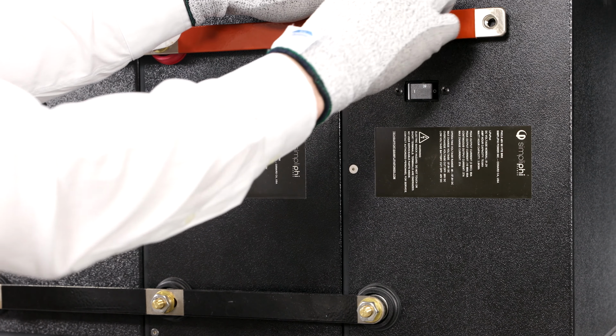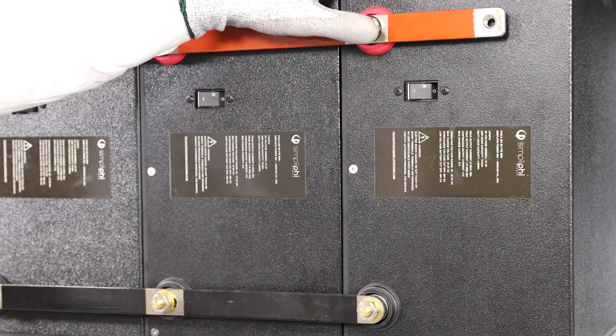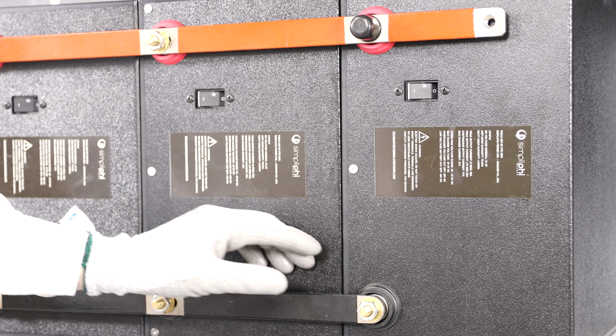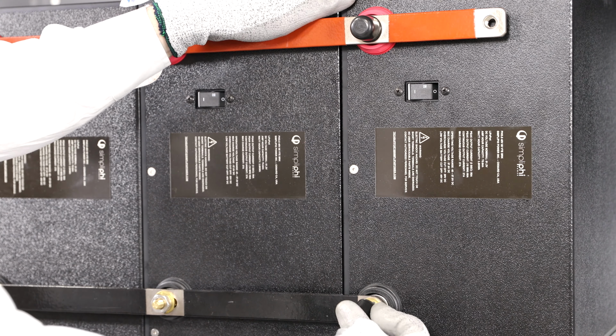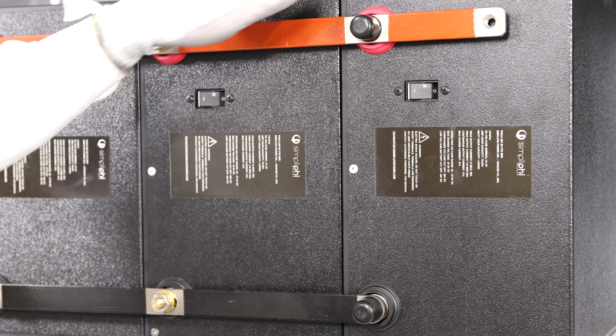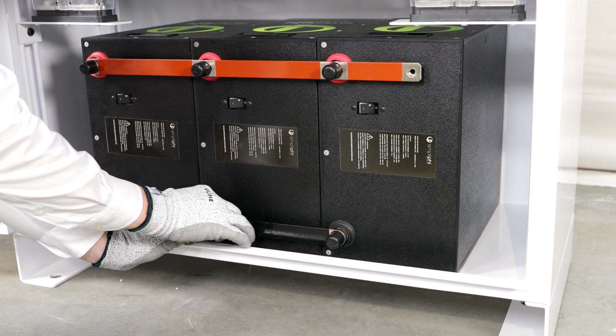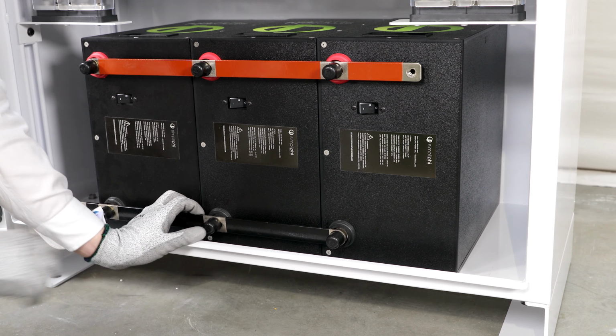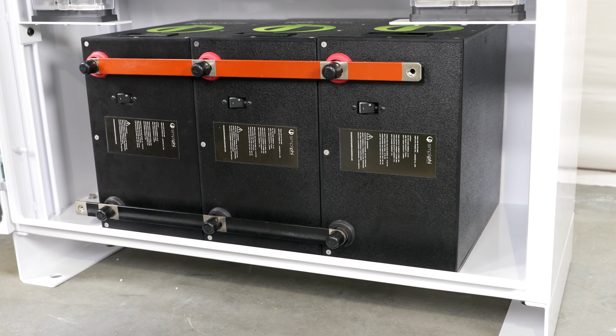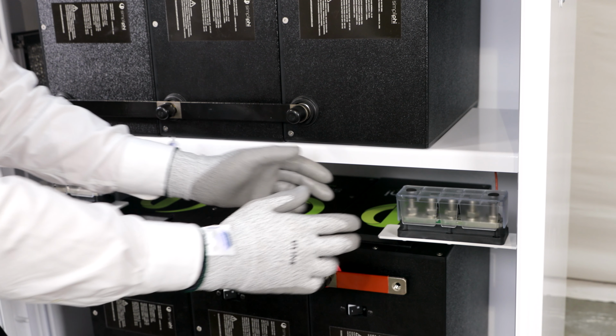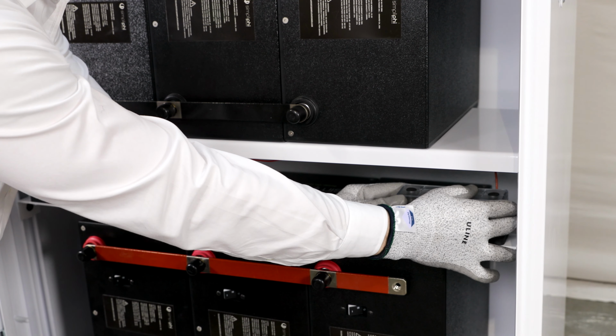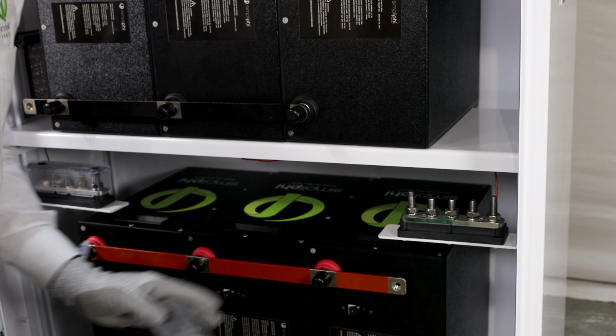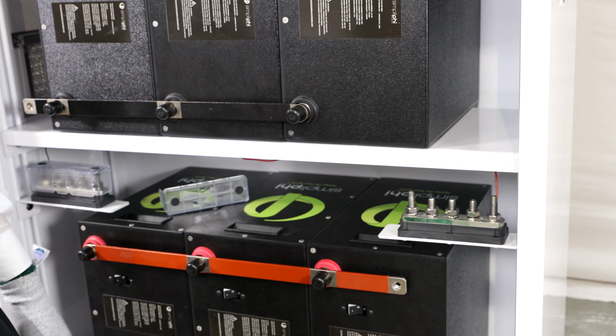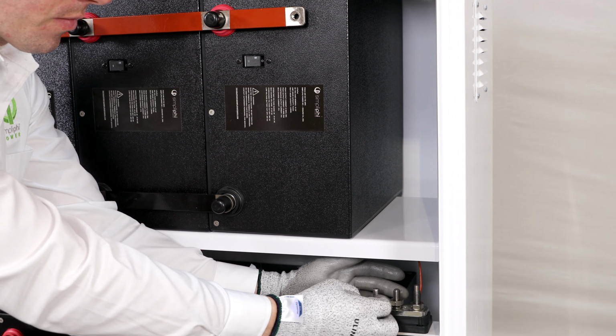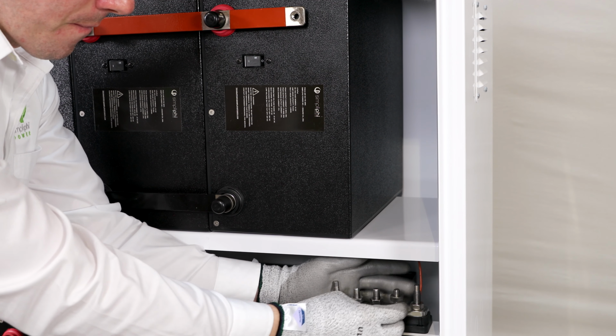After securing the bus bar to all battery terminals, place the black terminal caps over the terminals, ensuring to cover the 3/8-inch hex nut. Now that all the batteries are paralleled with the bus bar secured, prepare the 5-point terminal block for landing the cabling. Remove the clear plastic 5-point terminal block cover by lifting straight off the top. Remove the nut and lock washer from the 5-point terminal block.